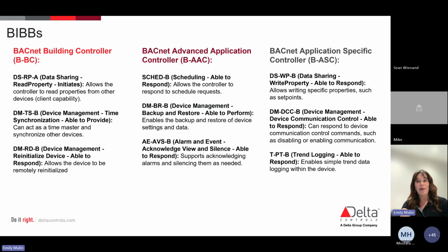We talked a little bit about the BIBBs, those BACnet interoperability building blocks, and this is by no means a breadth of categories here, but these are just a few that I picked out from the BTL website between the three different categories. And again, this is what's really shaping those device profiles. So something that's in a BACnet building controller might be the ability to share data between multiple different controllers, or you might not need that in an application-specific controller.